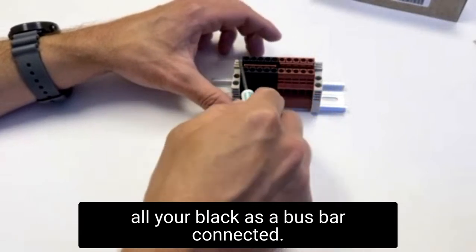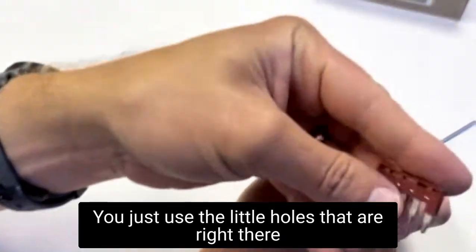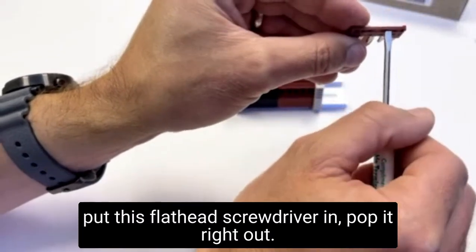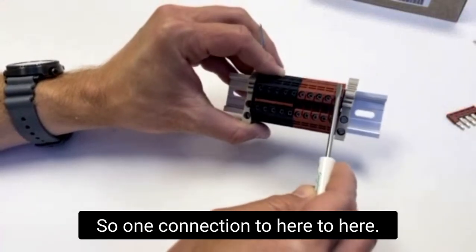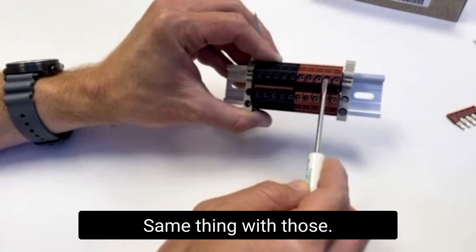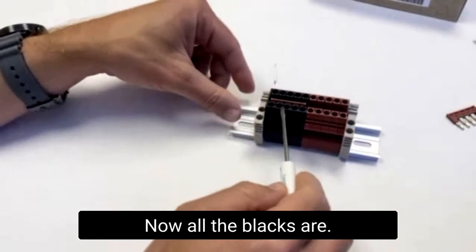If you ever wanted to, let's say you want all your blacks as a bus bar connected, but you didn't want the red ones connected, you just use the little holes that are right there or the little ridge or holes that you can put this flathead screwdriver in, pop it right out. Now these are all single in, single out, so one connection to here to here. They just aren't connected down the line. All the blacks are because they still have the jumpers in there.